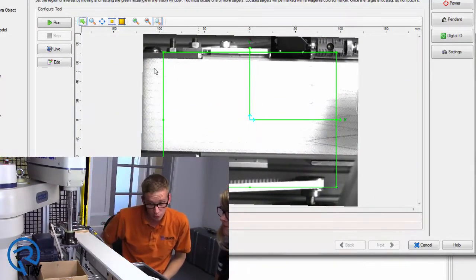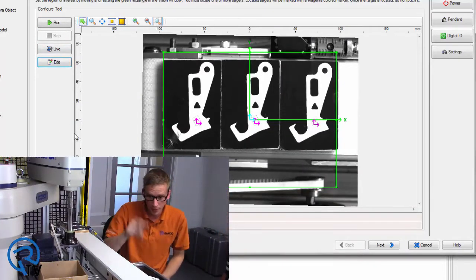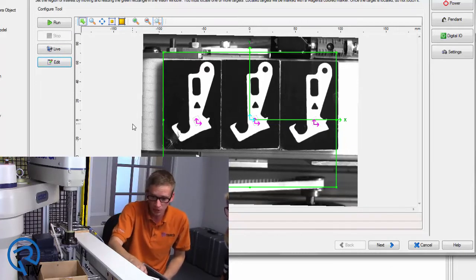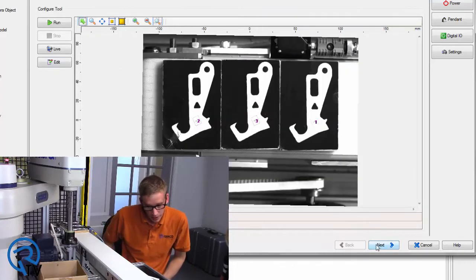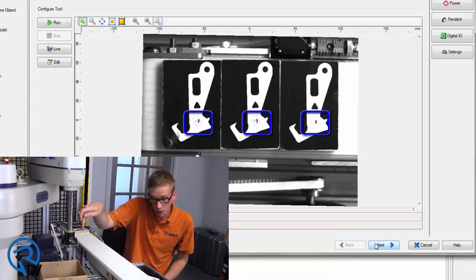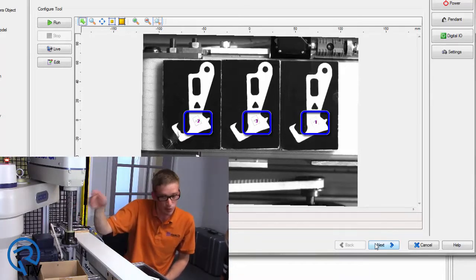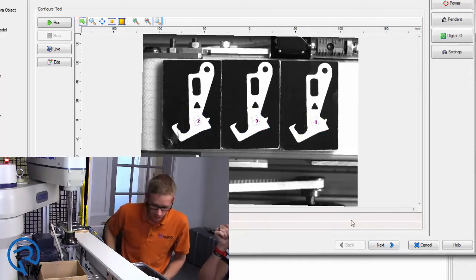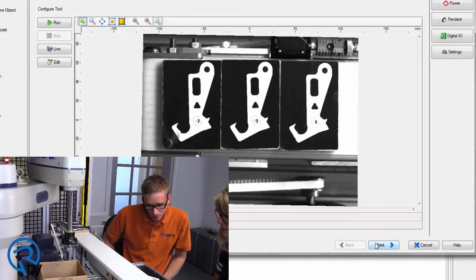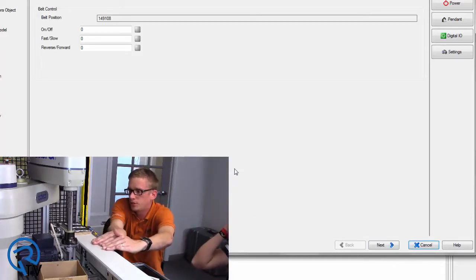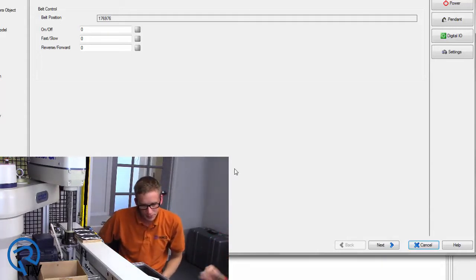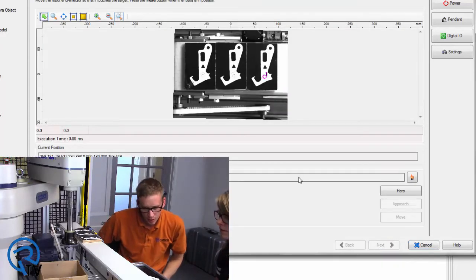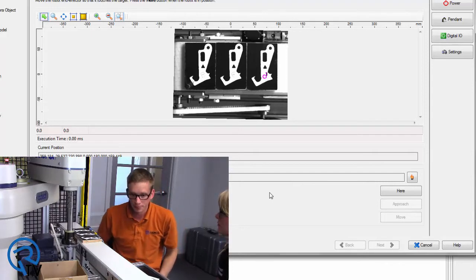Now we're going to teach the downstream pick limit. This is the furthest point the robot is allowed to pick up a part. I'll raise this up, press and hold the brake release, and raise that up. I'd say roughly that, about as far as we can go before the robot - because the robot has to be able to release the part over in the place position and get back in time. By the time it gets over there, it's going to be too late. And should I do like right at the edge of the conveyor? Right at the edge of the conveyor, because we're teaching the other side of the conveyor now. Here and next. So now let's test to make sure the conveyor tracking is working. I'm going to pick this up, move it slightly above the conveyor. Now turn the robot on, press that button. Now press start tracking. So now if I move the conveyor, the robot's going to move with it and follow it exactly. And it's doing that. Cool. Stop and then press next.